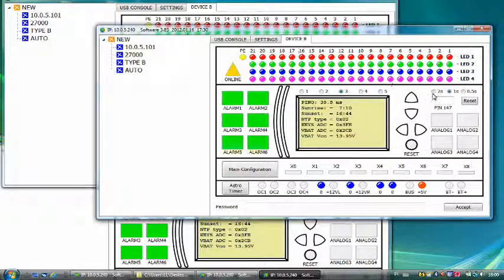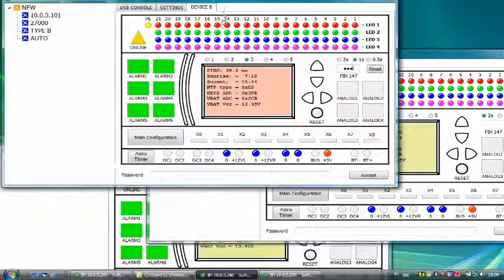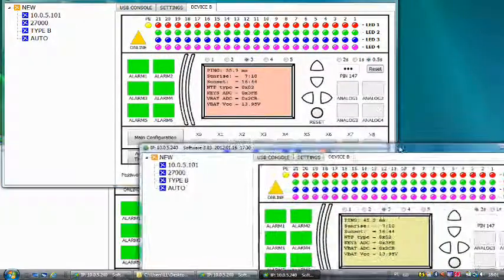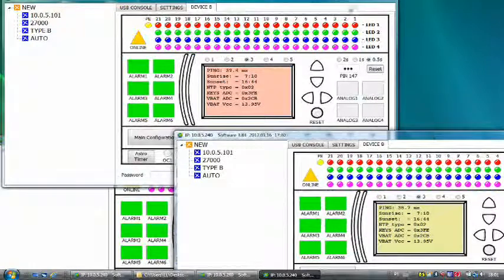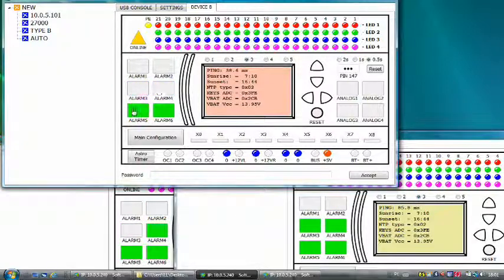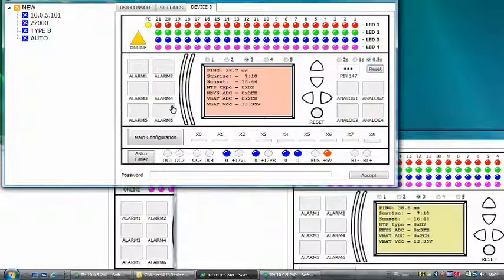Now, switch these settings in two of the windows to two seconds. It should be at half a second in the other window. Now, if you switch off or on the alarms, you will see that the other windows react slower. This is because this setting defines how often the software asks the relay to update its status. If you set the windows back to half a second, you will see that they respond much quicker.